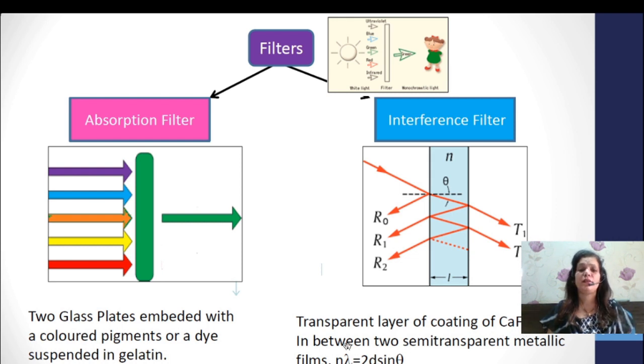Here, when a ray of light is passed through this sheet, it transmits radiation, and some amount of radiation is reflected back. Whatever amount of reflected radiation undergoes constructive interference is added at this node and passes again to transmit the radiation.